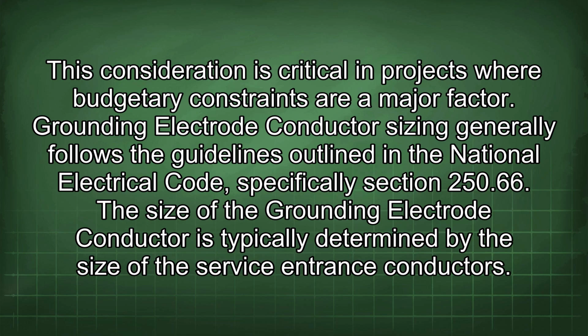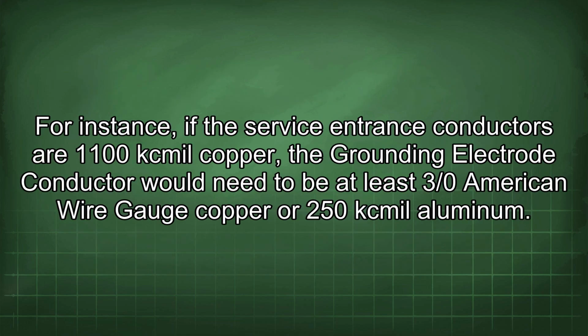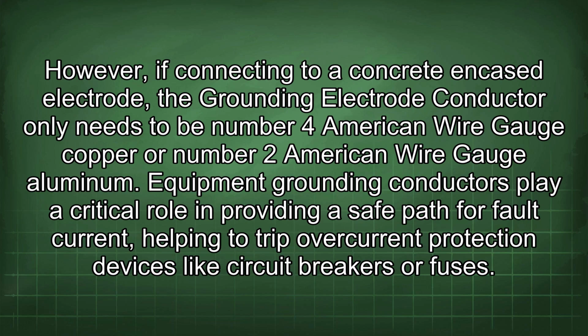Grounding electrode conductor sizing generally follows the guidelines outlined in the National Electrical Code, specifically section 250.66. The size of the grounding electrode conductor is typically determined by the size of the service entrance conductors. For instance, if the service entrance conductors are 1100 kcmil copper, the grounding electrode conductor would need to be at least 3/0 American wire gauge copper or 250 kcmil aluminum. However, if connecting to a concrete encased electrode, the grounding electrode conductor only needs to be number 4 American wire gauge copper or number 2 American wire gauge aluminum.